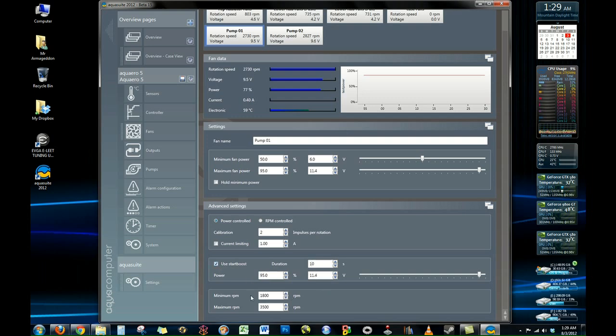Now it's very important to use the start boost with the pump. Reason being is that if you have your curve set up to only operate at like 50% at a lower temperature, your pump may not actually spin up at that lower voltage starting. So the start boost allows it to kick on to a higher voltage at the very beginning. Run for about 10 seconds and then it can drop down to whatever your controller curve has specified.